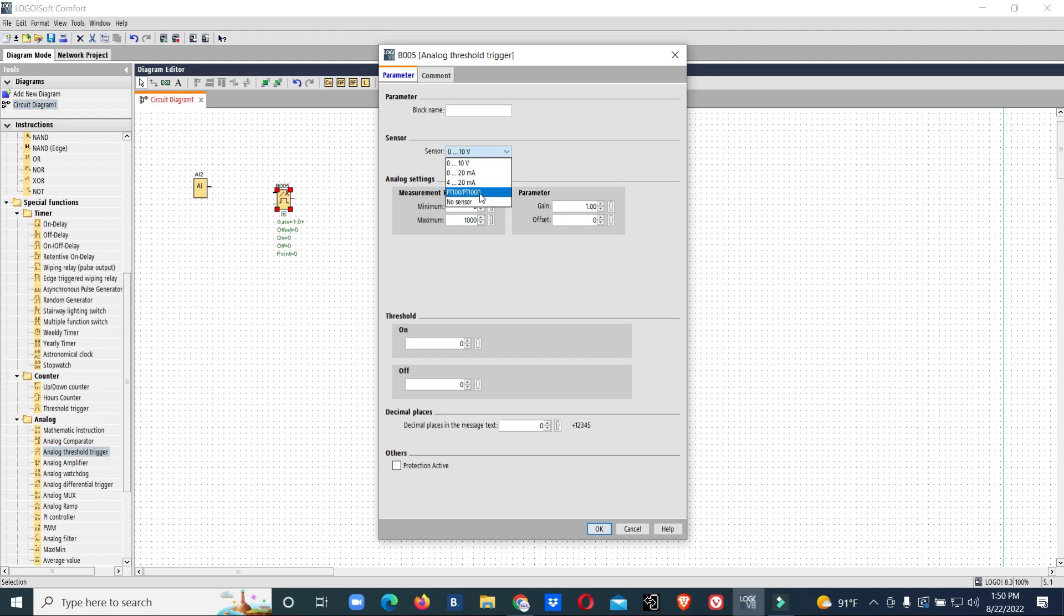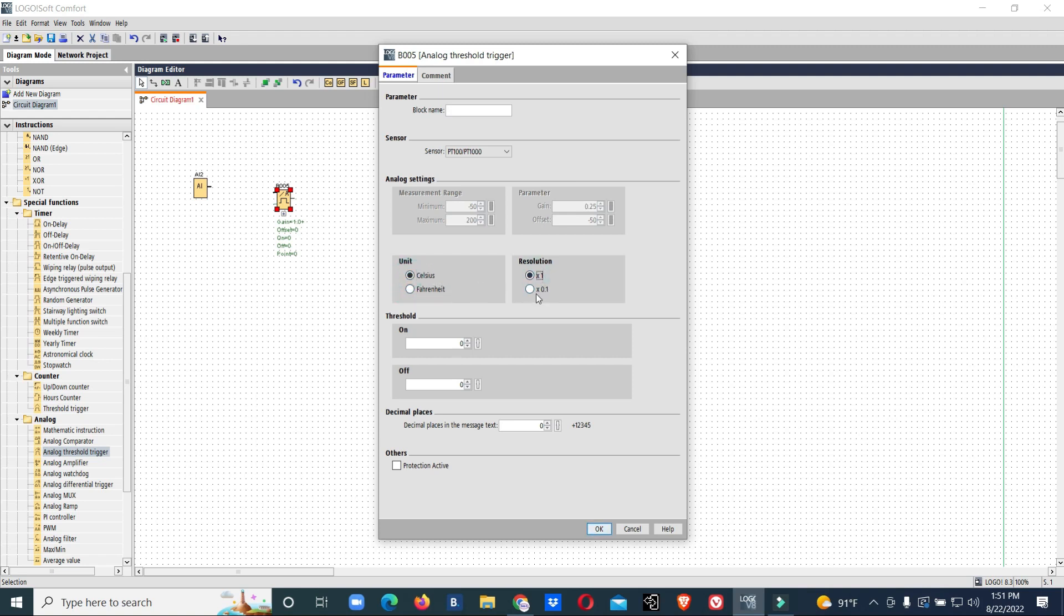The sensor is PT1000. Once you connect any sensor to this LOGO, the PT1000 will detect automatically. We have unit selection in Celsius and the resolution minus 50 to 200. Our range is 80 to 90, so we'll go for minus 50 to 200.